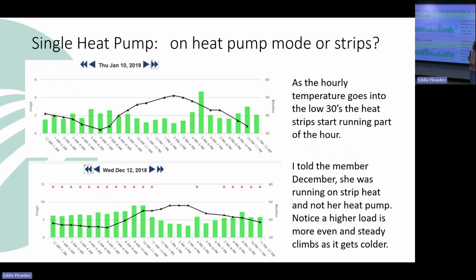This is an example of a home in a country club neighborhood, and they had this member. She had set her thermostat on emergency heat instead of on the heat pump or automatic mode. And if you look, these are basically the same temperature on the days. If you look at the bottom, this is when she was running on the electric resistive or electric furnace mode, and you see her power use in the middle of the night when it's down and close to freezing is 7, 8, 9 kilowatt hours, and actually, it grows as it gets closer to daylight. And then when you're running the heat pump mode, it's running less than 2 kilowatt hours, and it's balancing to have a little bit of strip heat running, just barely part of the hour, but it's on that compressor throughout the whole night. Way, way, way lower power use in the heat pump mode.